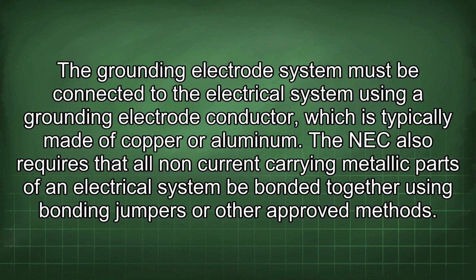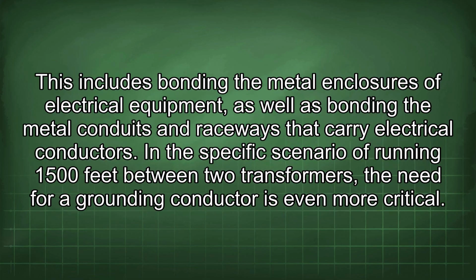The grounding electrode system must be connected to the electrical system using a grounding electrode conductor, which is typically made of copper or aluminum. The NEC also requires that all non-current carrying metallic parts of an electrical system be bonded together using bonding jumpers or other approved methods. This includes bonding the metal enclosures of electrical equipment, as well as bonding the metal conduits and raceways that carry electrical conductors.